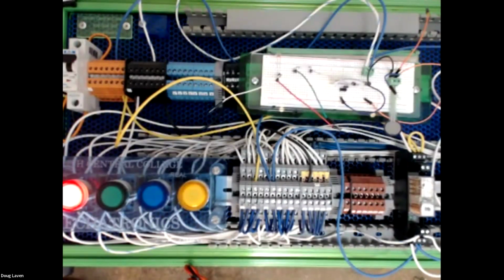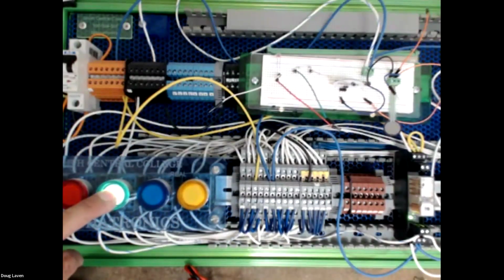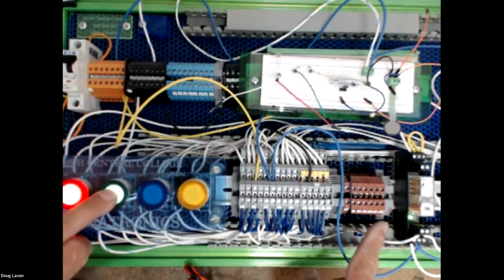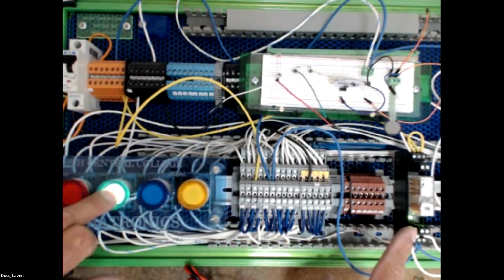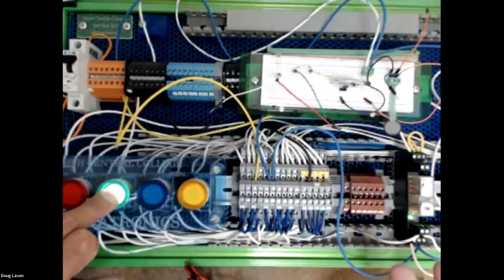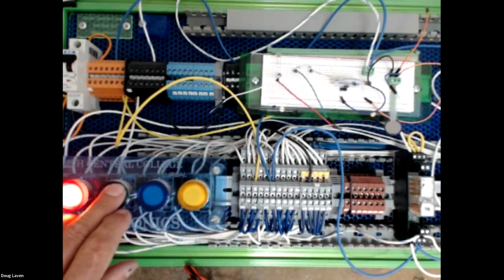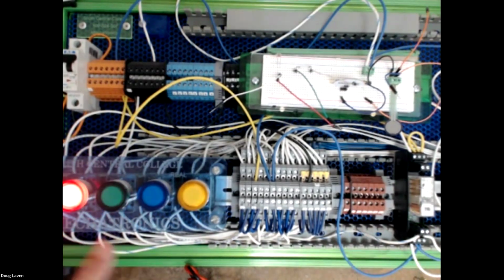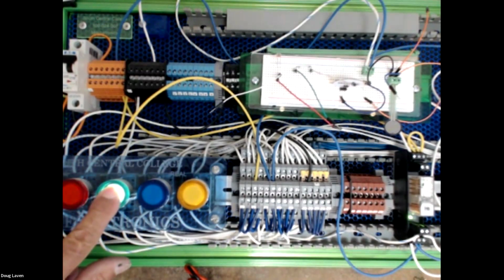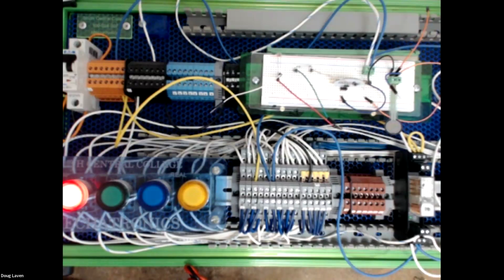Well, you see my red light on, right? Yeah. So when I push the green button, you see the indicator light over here on my relay, that's telling me it's energized. If I had those reversed, A1 plus and A2, it wouldn't work. So normally closed contacts, normally open contacts. And when I release, it goes back to its default, or at rest. This is on and this is off. So now the question is, how do we make this stay on when I momentarily push that button?